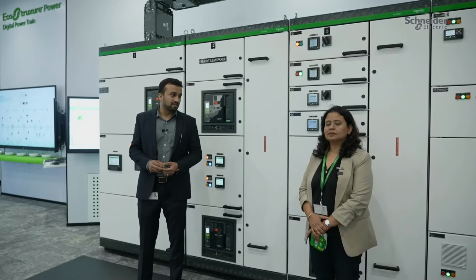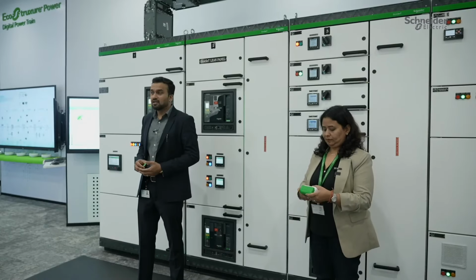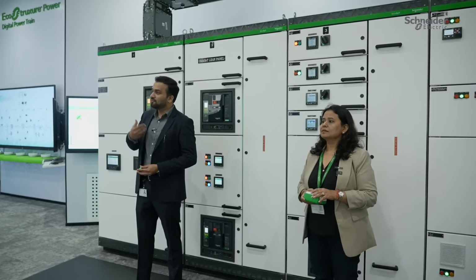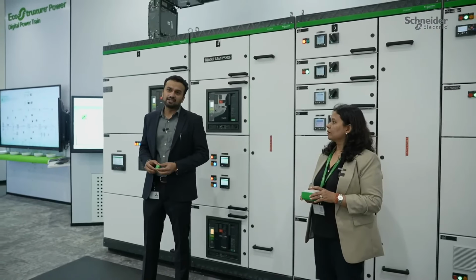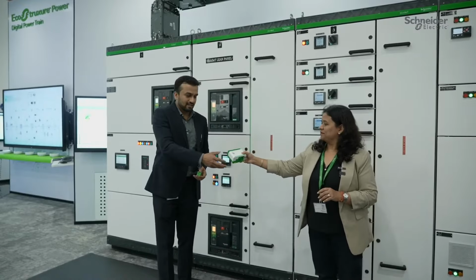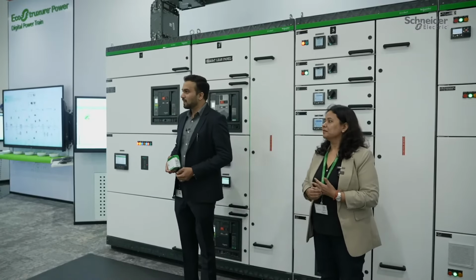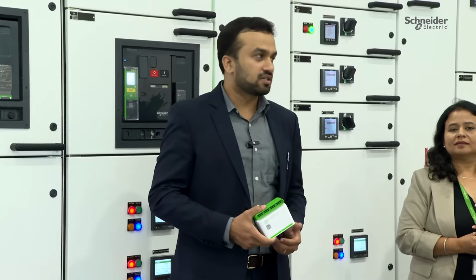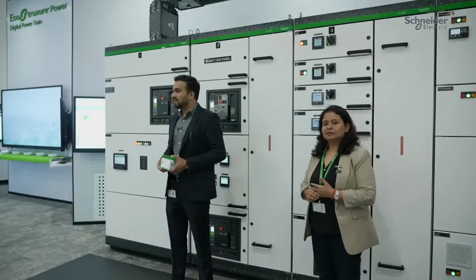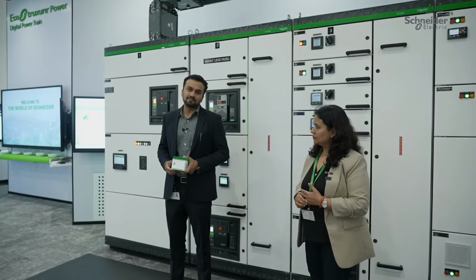Most of our electrical distribution is also through cables. Insulation damage causes frequent problems. Even home fires begin as a simple spark from insulation damage. That's where we bring the third sense of measurement, the sense of smell. We call this the nose of the panel, which detects any smoke from the insulation of wires in the cable alleys, making sure it's detected well in advance to prevent any catastrophic effect in the ecosystem.